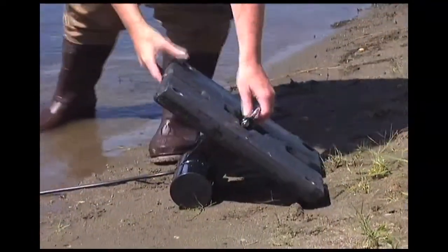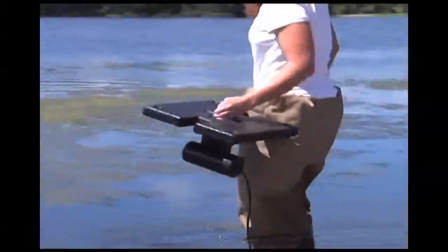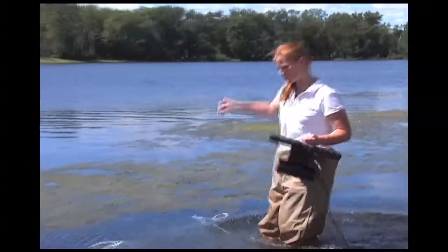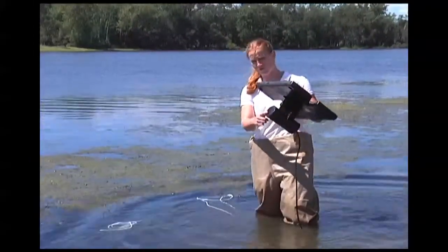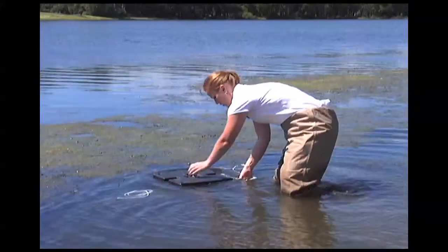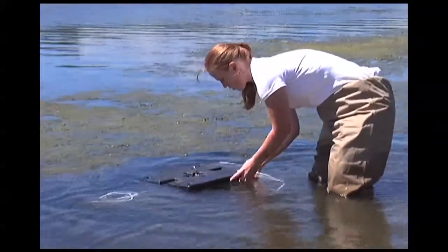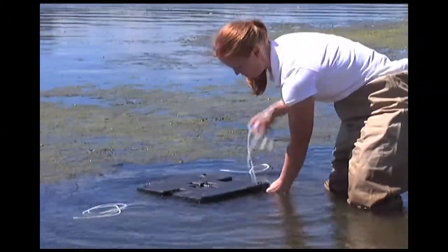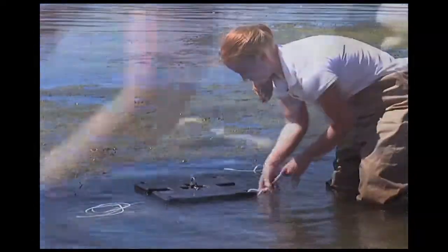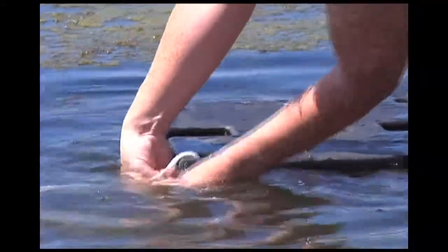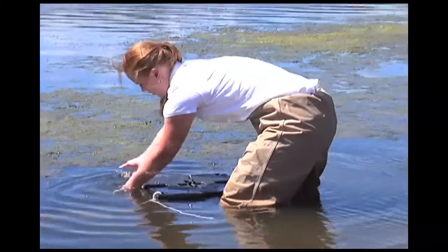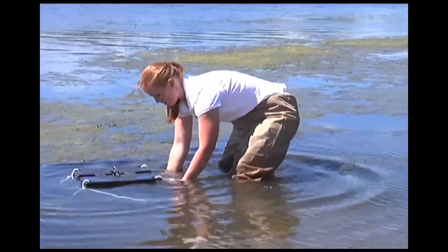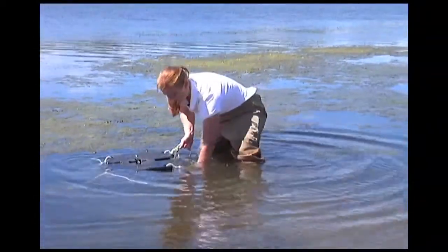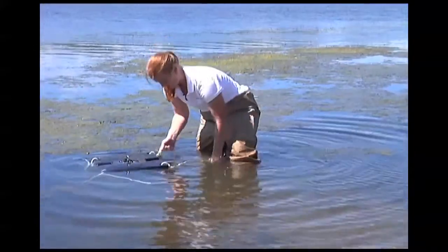Next, we're going to take our unit and place it into the water, using the ropes to secure it to the cinder blocks. You want to make sure that the transducer head or the flat part is facing out. We're going to use the ropes tied into the 4 corners of the float. Once the ropes have been secured to the float, we're going to reposition the cinder blocks to tighten up the length and make sure that the unit is facing in the right direction.